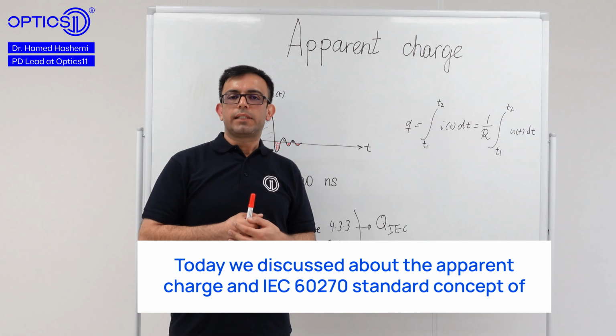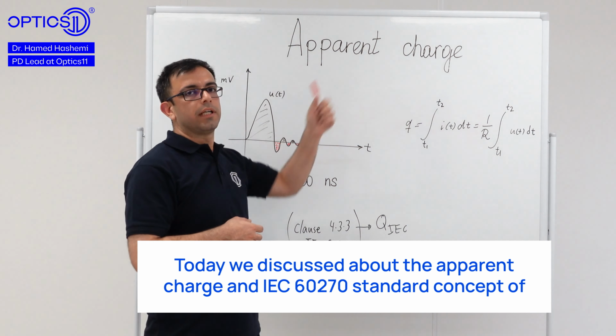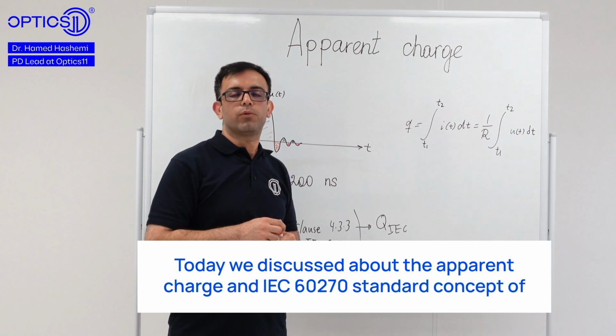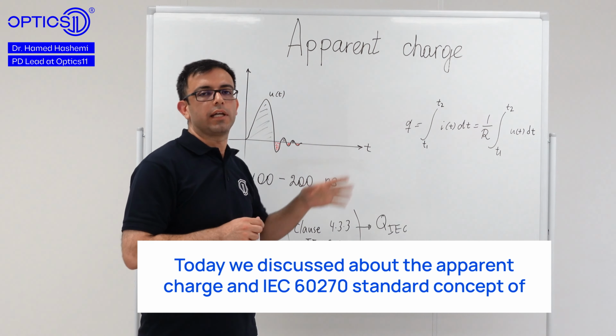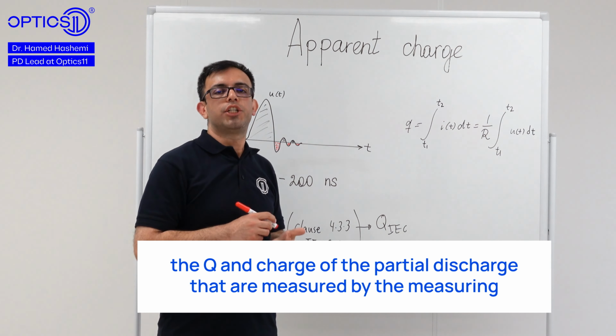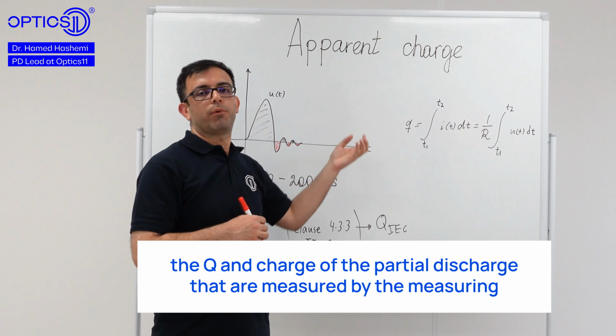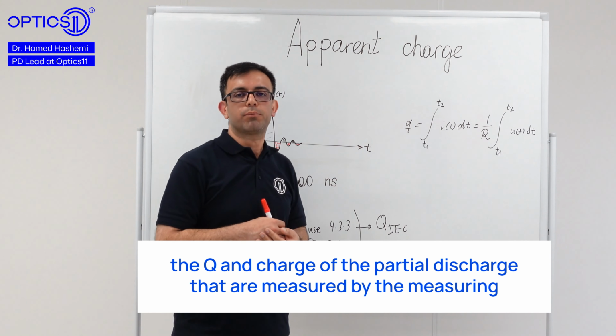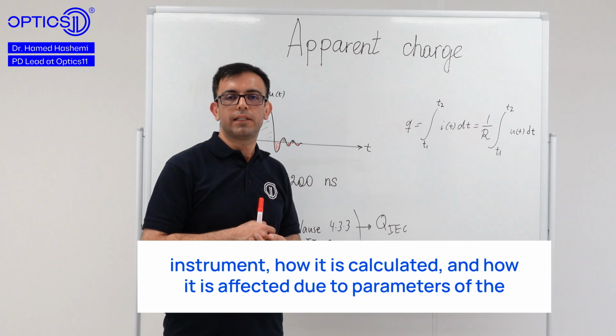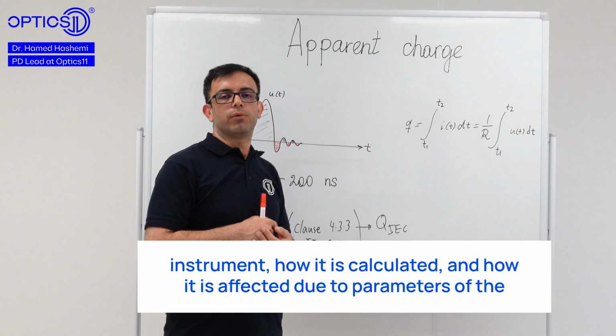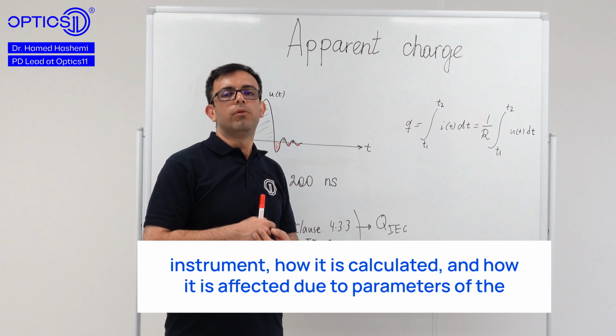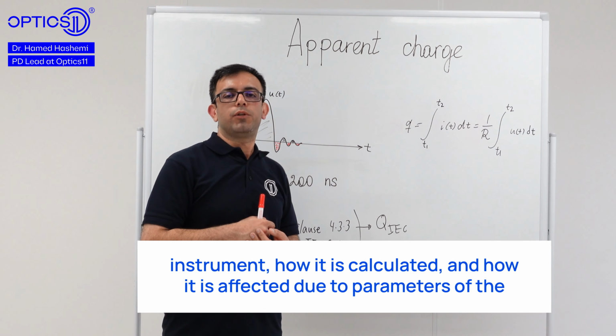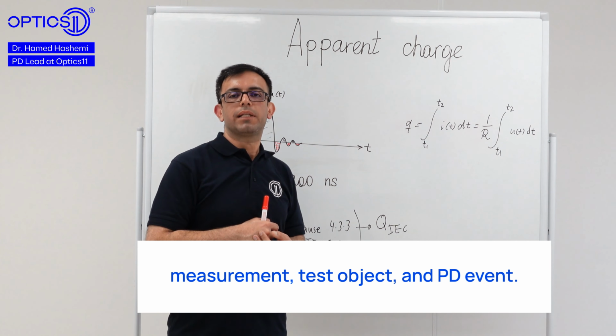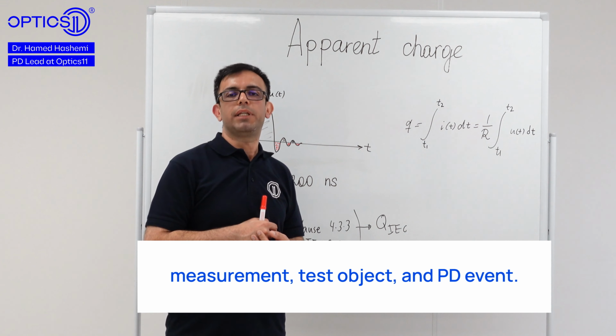Today we discussed the apparent charge and the IEC 60270 standard concepts of the Q and charge of the partial discharge that are measured by the measuring instrument, how it is calculated, and how it is affected by parameters of the measurement, test object, and PD events.